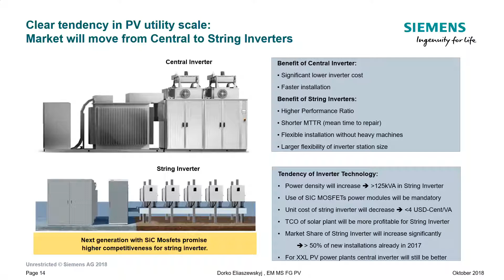The capex is a decisive point for central inverters, much lower than string inverters. But the OPEX and other parts, like preventive maintenance, are lower for string inverters. So case by case, you have to calculate if this or that is more profitable.